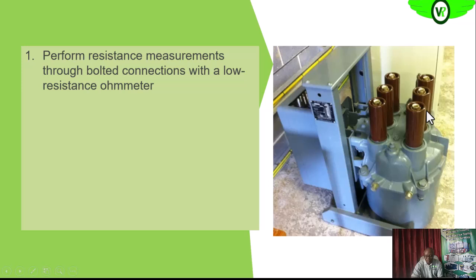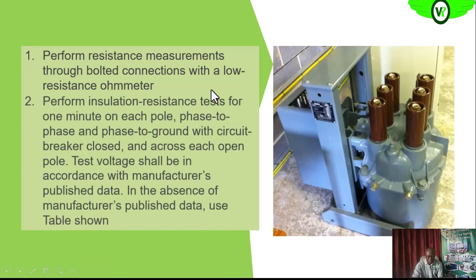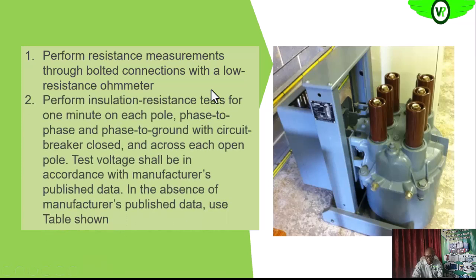As usual, we want it to be as low as much as possible. Should be zero, as close to zero or zero. Then we want to also perform insulation resistance test. The insulation between the phases, between phase 1 and 2, between 1 and 3, and 3 and 2. Okay, and then each of the phases to ground. So we'll do that when the breaker is closed, and when the breaker is open, we want to test the insulation between the contact. Okay, that is across each of the phase.